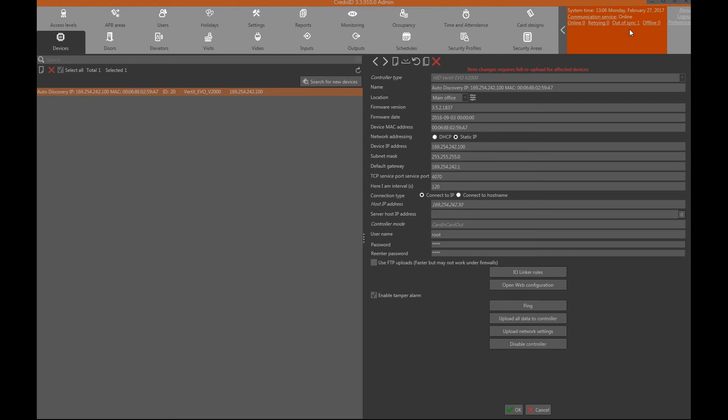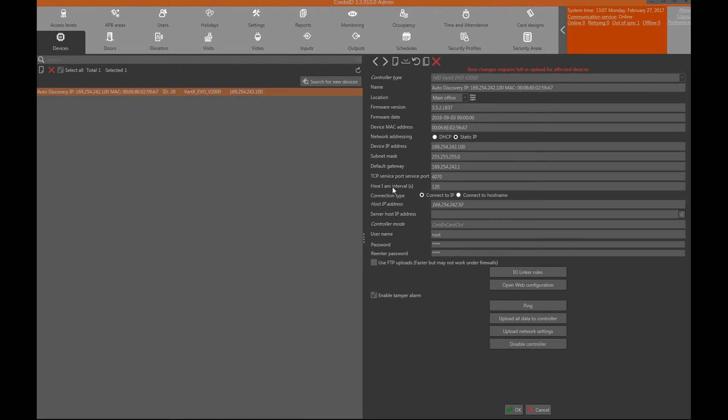Now before synchronizing the device with the software, settings have to be checked for the HID devices in the details panel as some settings might be incorrect. Usually there are two settings that get affected by this: heartbeat interval and HID user credentials. In my situation username and password are incorrect so I'll change them.